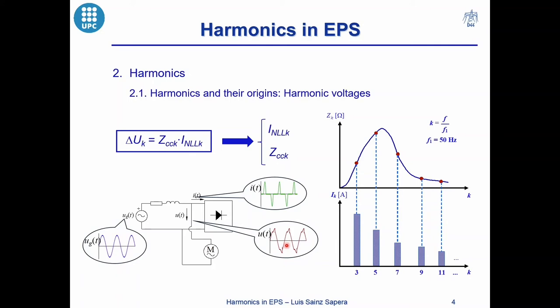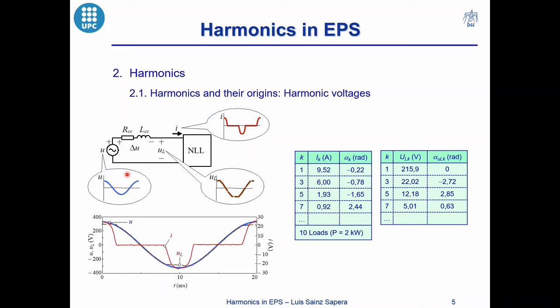In the next screen, there is an example of a sinusoidal supply voltage which feeds, through the impedance of the grid, 10 single-phase rectifiers of 2 kW each, consuming the non-sinusoidal current shown in the plot. The voltage at the nonlinear load terminals becomes non-sinusoidal due to the distorted currents consumed by the nonlinear load and the impedance of the grid. It can be seen that the load voltage has a flat zone matching with the peak of the current consumed by the single-phase rectifiers.